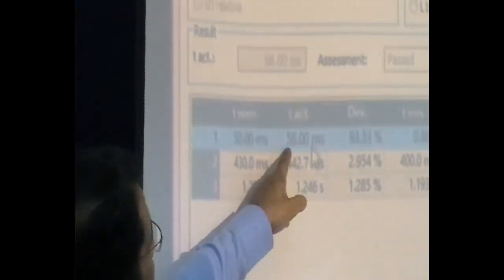The first one is in zone 1. This is the one. I'm expecting a trip in which time? Let's say the timing here should be 0. What is the actual time? We're looking at T actual. 58 milliseconds. Again, when we are saying 0, it's not literally 0 seconds.